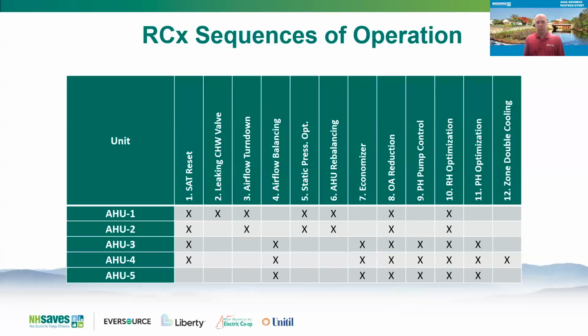That project included 12 sequences that were identified, varying from supply air temperature reset, leaking chill water valve, airflow turn down, just literally slowing down constant volume air handlers with cooling and reheat can be really cost effective. Balancing the airflows, knowing exactly what airflow you need in the space. Static pressure optimization, air handler rebalancing, economizer, making sure that your economizers are working properly and that you're benefiting from free cooling. When it's cold outside, which it is a lot in New Hampshire, you should be leveraging that cold air to provide free cooling.